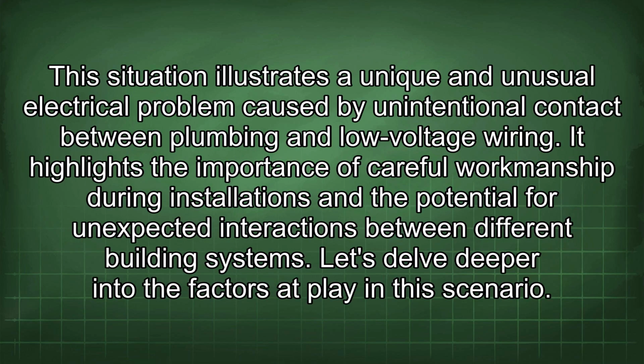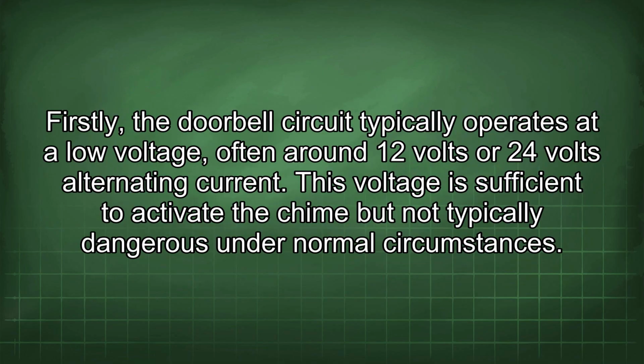This situation illustrates a unique and unusual electrical problem caused by an unintentional contact between plumbing and low-voltage wiring. It highlights the importance of careful workmanship during installations and the potential for unexpected interactions between different building systems. Let's delve deeper into the factors at play in this scenario. Firstly, the doorbell circuit typically operates at a low voltage, often around 12 volts or 24 volts alternating current. This voltage is sufficient to activate the chime, but not typically dangerous under normal circumstances.